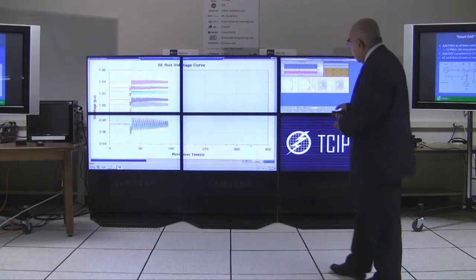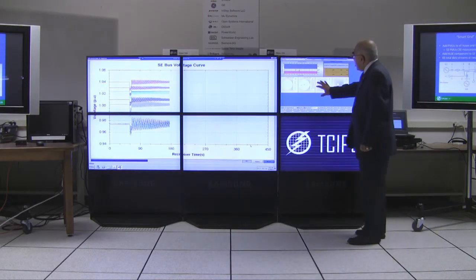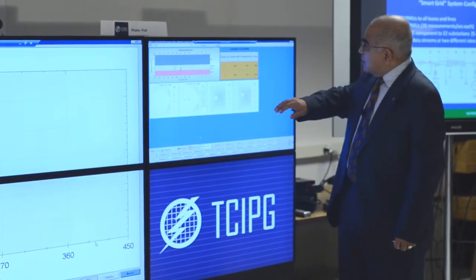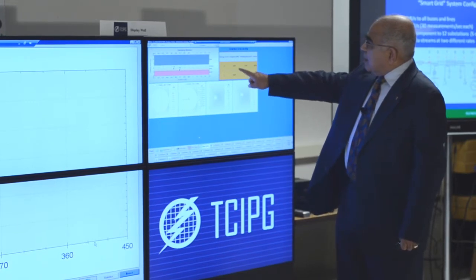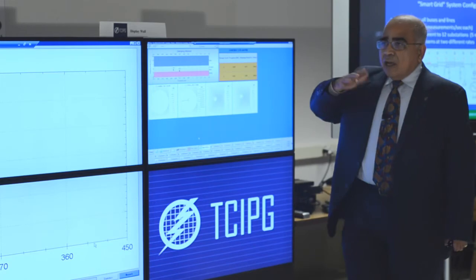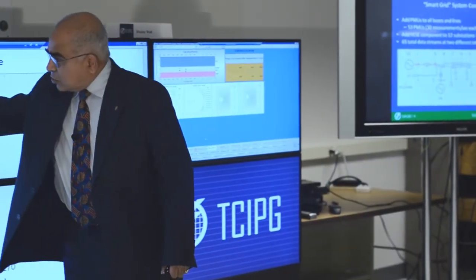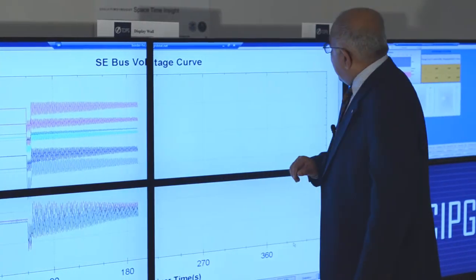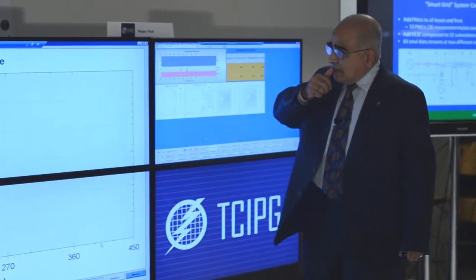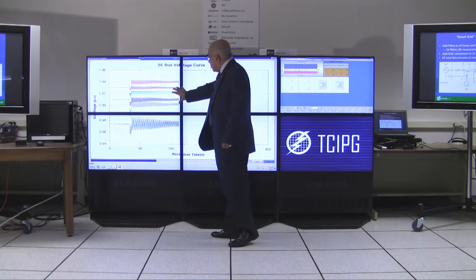In the oscillation monitor, this is showing the damping, and the damping is not in the red range, so it is okay. The frequency being picked up is 0.69 Hz and 0.55 Hz — those are two frequency modes of the oscillations. The oscillations have slow damping and are damping out, with a low damping ratio, close to the red part, but everything is dying out.